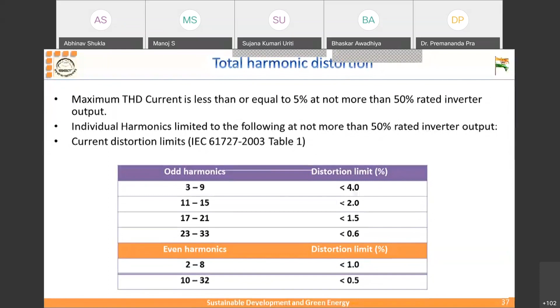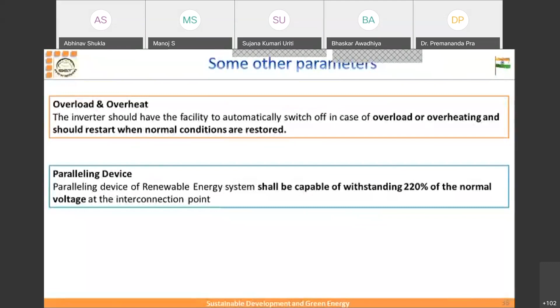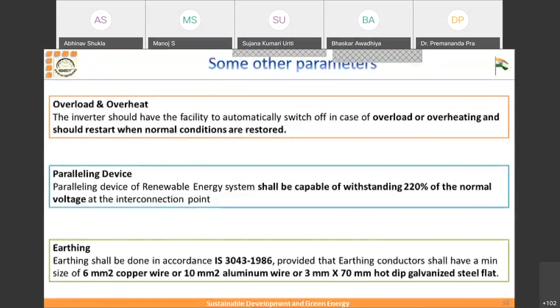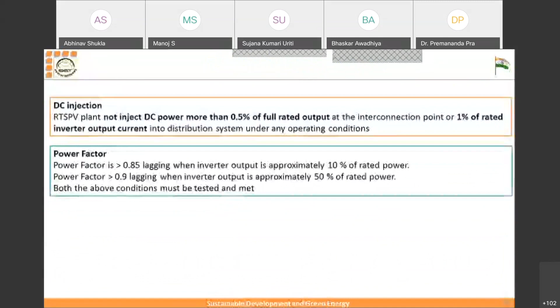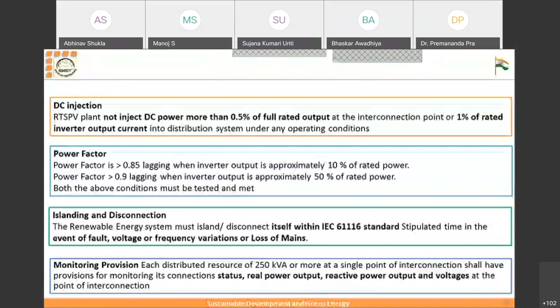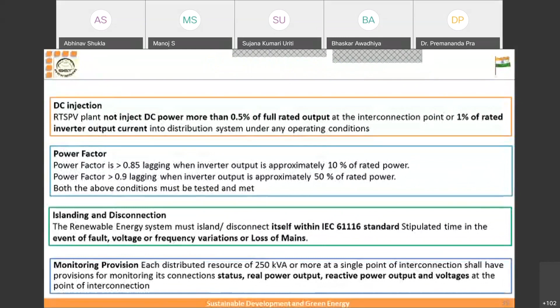Most probably in hospitals, where you have very good quality equipment. There are some other parameters, I'm not going much into that, but yes, for the earthing you have to follow IS 3043:1986. DC injection should not go beyond 0.5% of rated output. So this is the limit. Power factor 0.85, 0.9, and I think you all are aware of reactive and active power. So these are the regulations which are there.